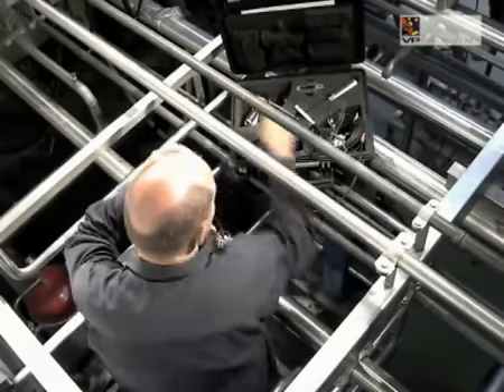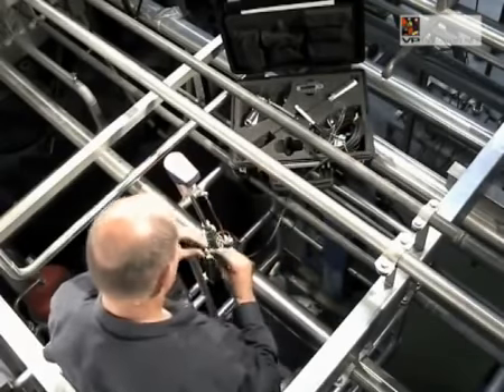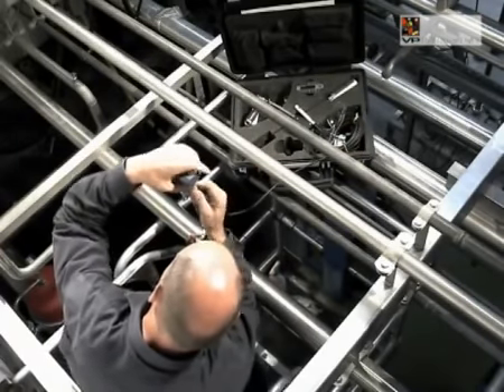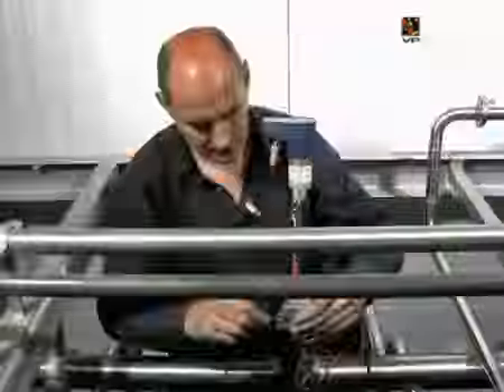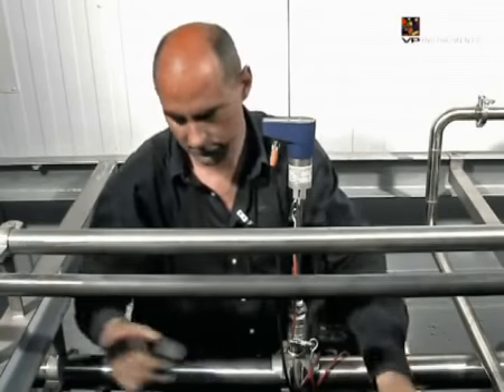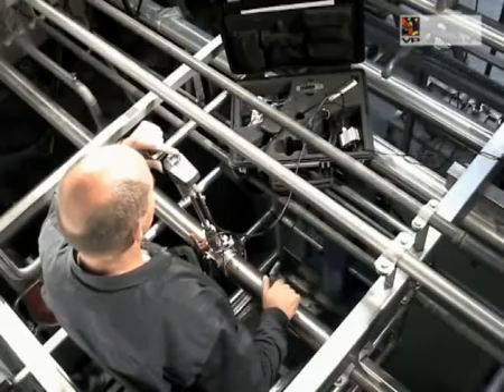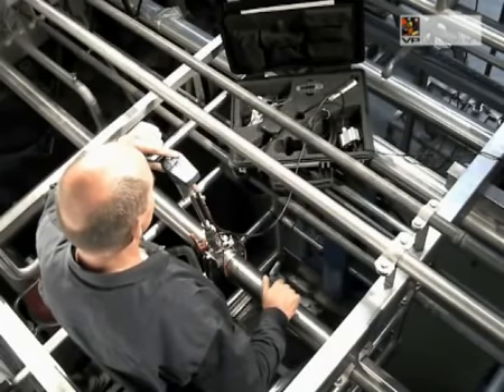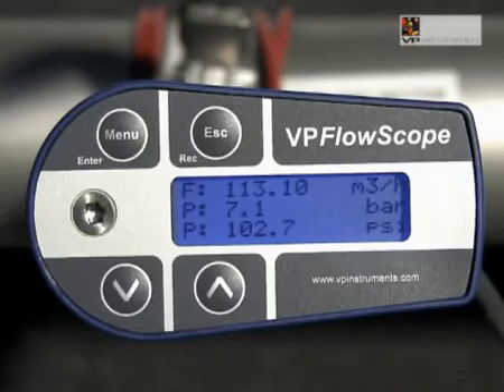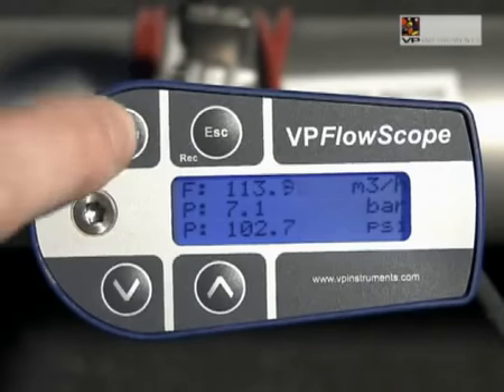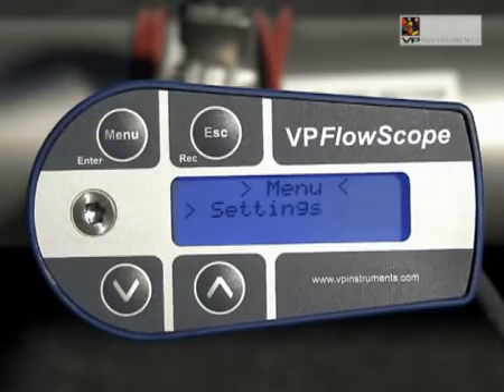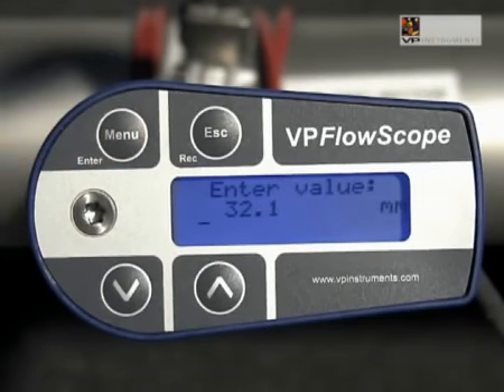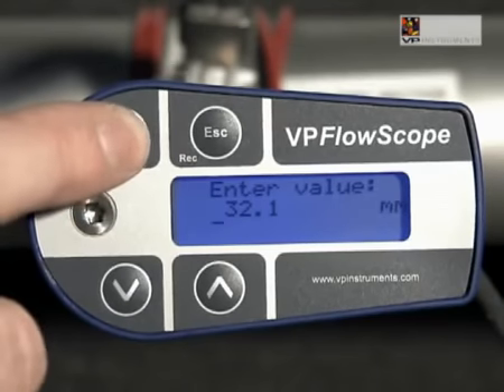Now tighten the compression fitting. Mount the display on the sensor module. Make sure that it slides completely over the O-ring seal, then fix the screw on top. Align the VPFlowScope with the flow direction. Tighten the compression fitting. Take the cable with the interface box and connect it to the VPFlowScope. Connect the power supply. The display of the VPFlowScope lights up and shows real-time information.